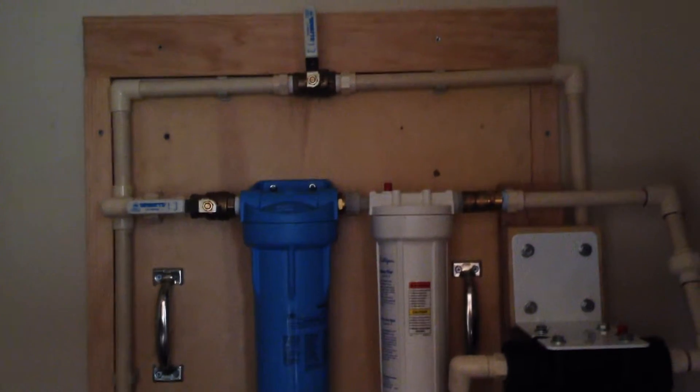Six cans of ceramic high flow — it's got a pretty good flow. Right now it's going through. You can see it's coming up from the tank. I had the water running so the pump is on. It's got an internal pressure switch in the pump. We're running at about 40 psi. Got a little pressure tank. There's a bypass preventer, backflow preventer down there.